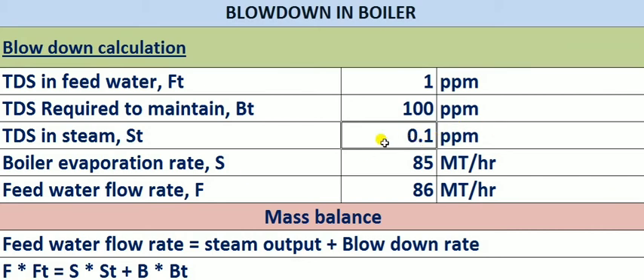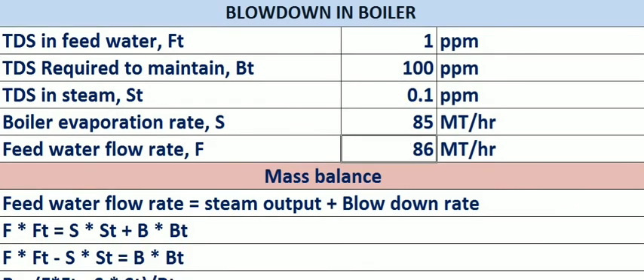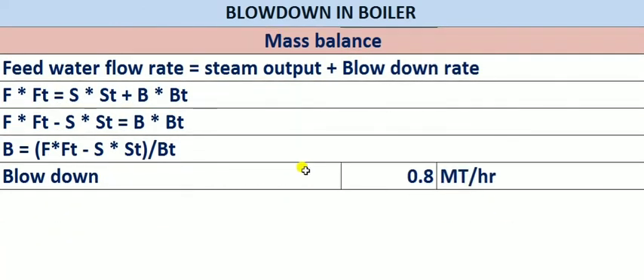TDS in the steam: normally there is condensation from the steam sampling, and from that condensate we measure the TDS — in our case it is 0.1 ppm. The steam output flow rate (evaporation rate) of the boiler is 85 tons per hour, and the feed water flow rate is 86 tons per hour. For the formula derivation, we use a mass balance: feed water input equals steam output plus blowdown rate. Steam leakage losses are not considered in this typical case.